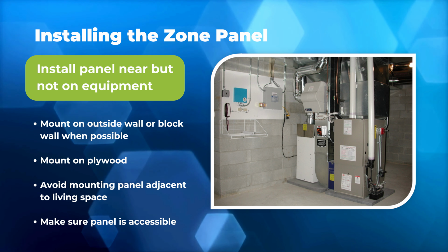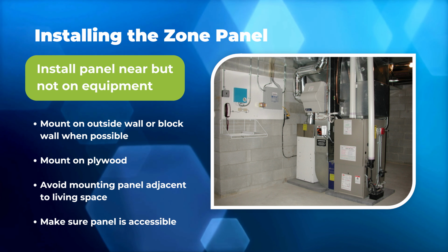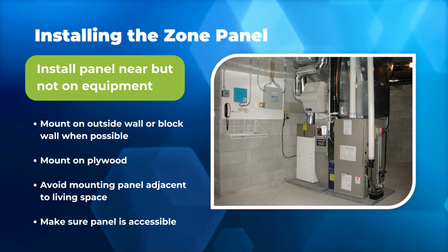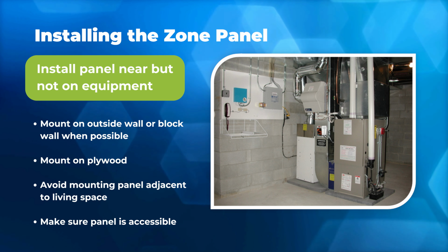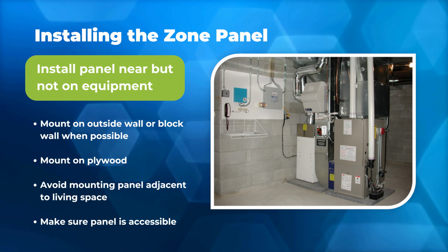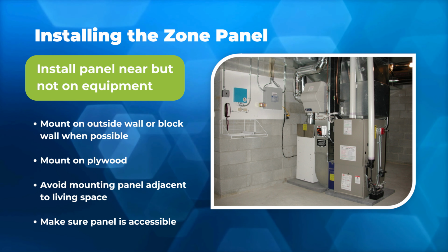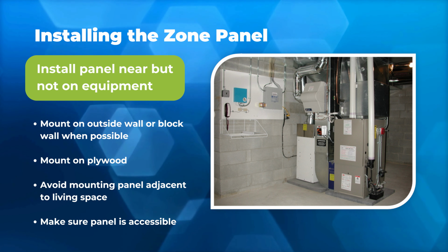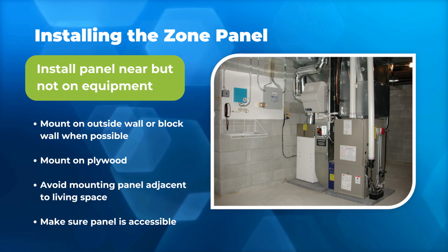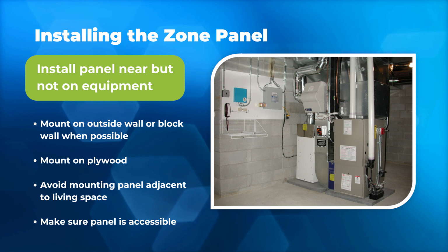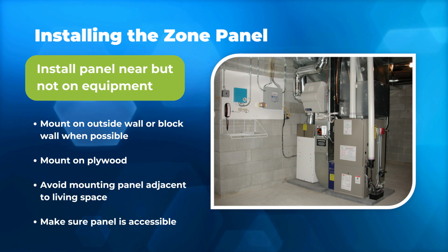So whenever possible, mount to a block wall. If not, you're going to want to at least cover 2 joist spaces with the 3/4 inch plywood and then mount your panel to that. And just a tech tip, vibration pads are a lifesaver. I used them all the time when I was in the field. You put a couple of those behind that and you will have very little noise whatsoever.